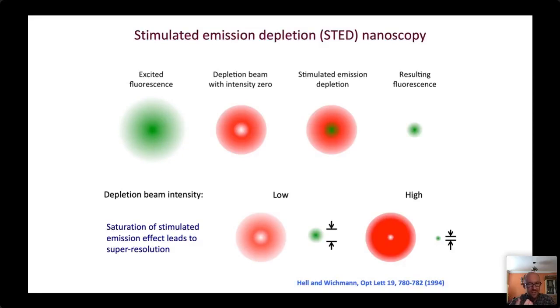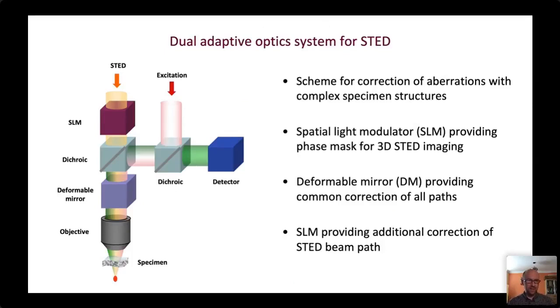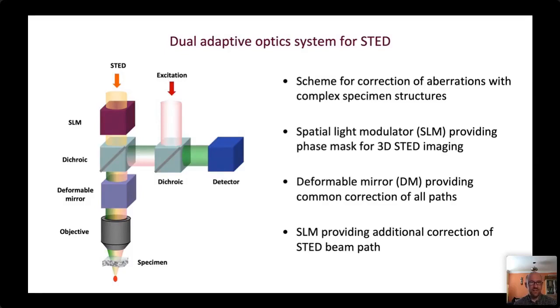Three-dimensionally resolved STED microscopy is more susceptible to aberrations. Our STED microscope has an excitation beam and an emission path constituting a confocal scanning microscope, plus a depletion path through a spatial light modulator which shapes the beam to have zero intensity at the center and also performs some aberration correction. A deformable mirror in the common path corrects aberrations in the excitation, detection, and depletion beam paths, and we use this alongside our image-based sensorless adaptive optics routines to correct for specimen-induced aberrations.